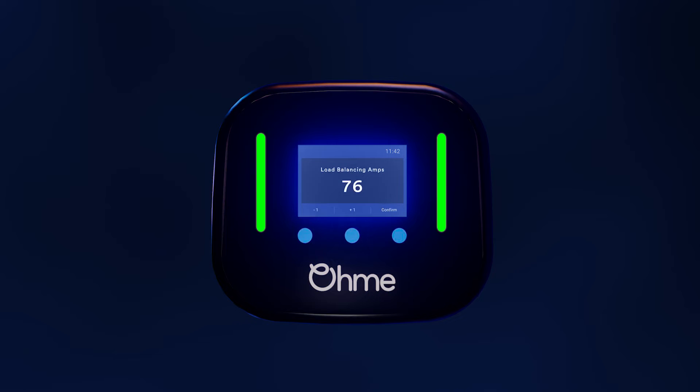Use the blue buttons to adjust the settings and continue to the next screen, where you'll be prompted to test the RCDs. The RCD test will auto-reset every two seconds. Click Exit Setup once setup is complete.